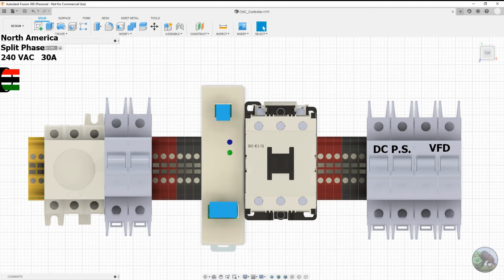into the wall. And I'm in North America, so this is split phase AC. And this plug is 240 volt AC 30 amp. So this is a 3-wire, and so we have 2 hot wires and 1 ground. And so there is no neutral. And so the first thing that happens is that ground wire is bound to the ground terminal block. And it's super critical that this happen first, and that this ground wire not go through a rotary disconnect or any other kind of switch. It needs to be constantly in contact with the chassis ground of your enclosure.